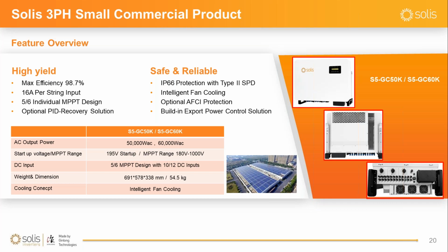And for the weight and dimension shown here, the weight is around 54.5 kilograms. It has intelligent fan cooling. As you can see, there are 3 fans at the bottom to help the cooling of the inverter, and also 3 sets of the DC switch for disconnecting from the PV side. And also for this inverter, we have the optional PID recovery solution that we will talk about later in the next slide. And then the protection rating is IP66, which is higher than previous products.